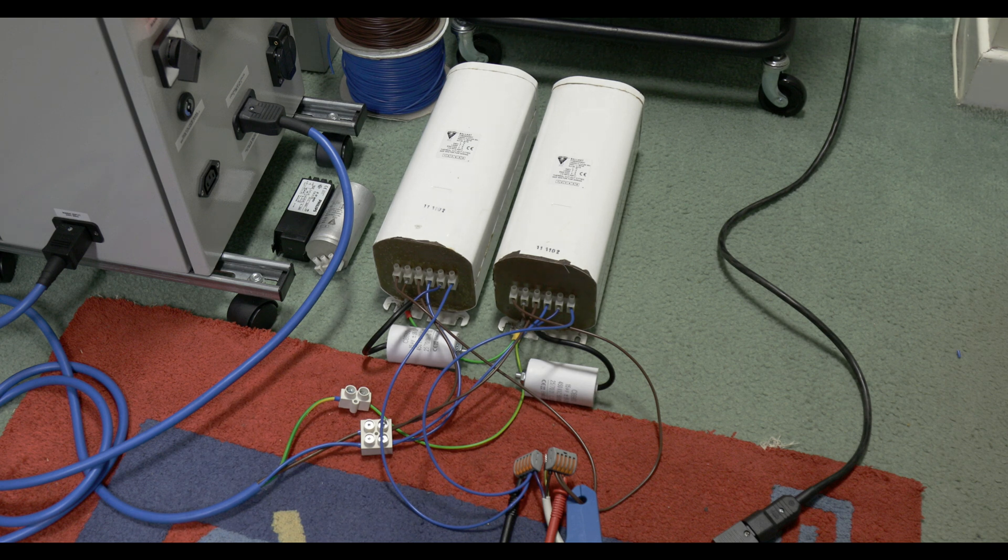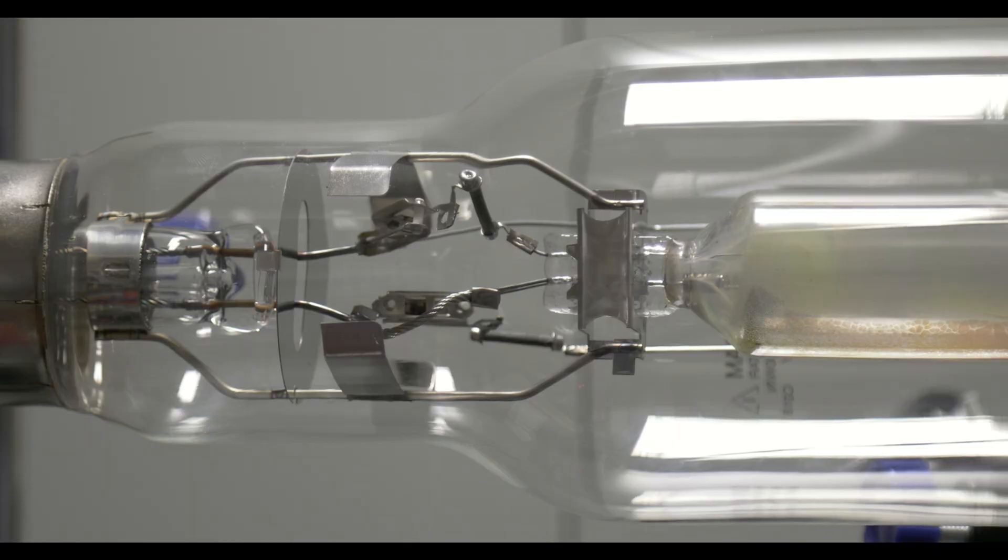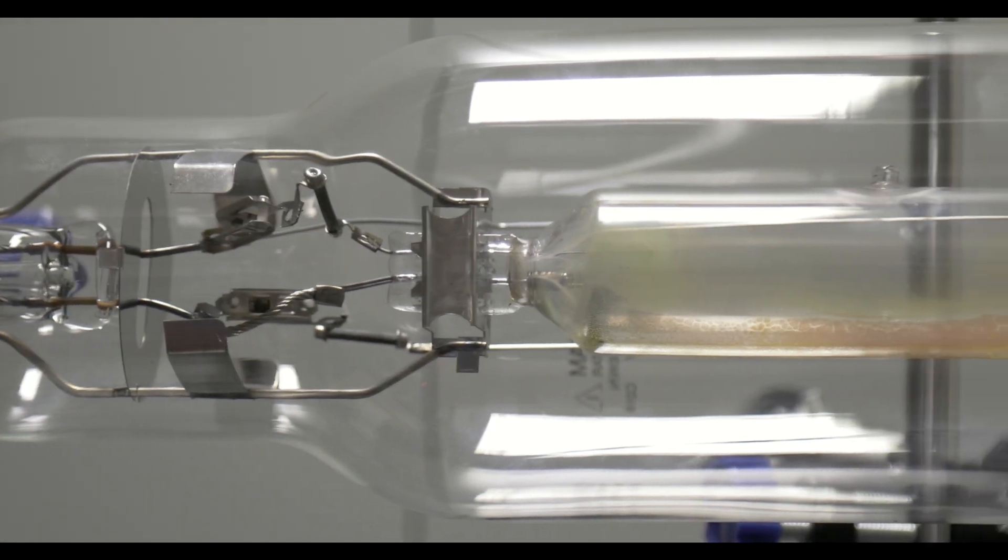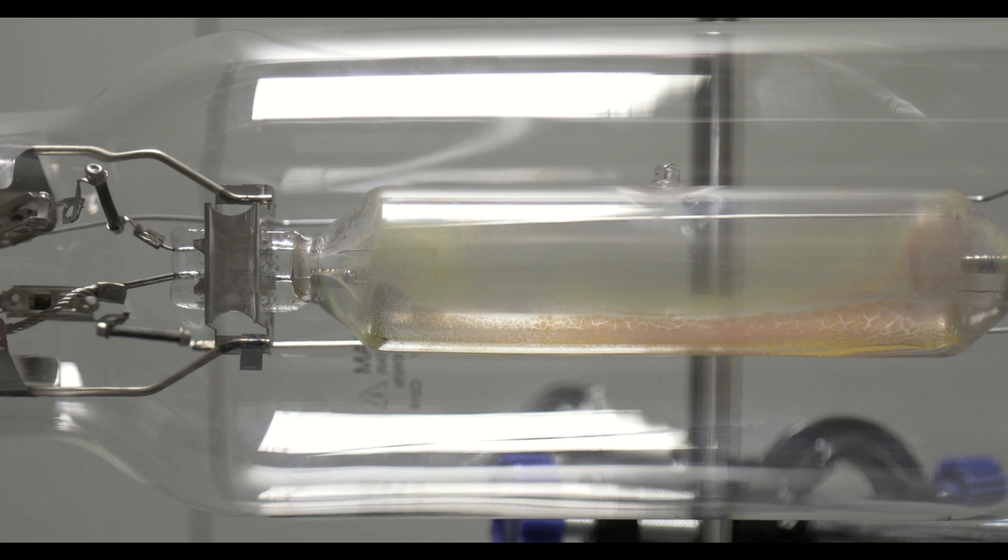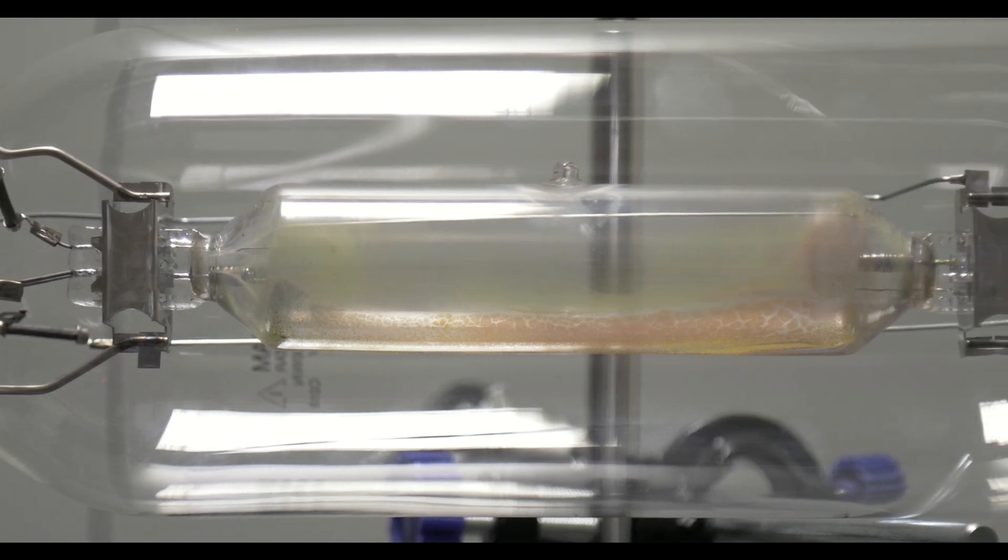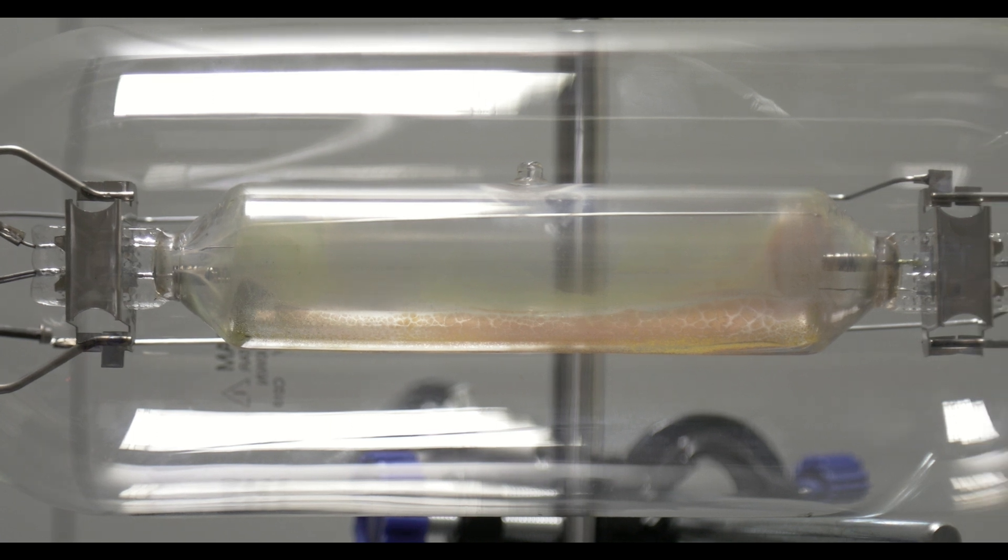Just a quick look at the starting resistors. They feed an auxiliary electrode, one at either end of the arc tube, and they are fitted with bimetallic switches which when the lamp runs up they open and remove them from the circuit. Obviously we can see the arc tube there, full of the various metal halide salts, and you can just make out those tiny auxiliary electrodes.